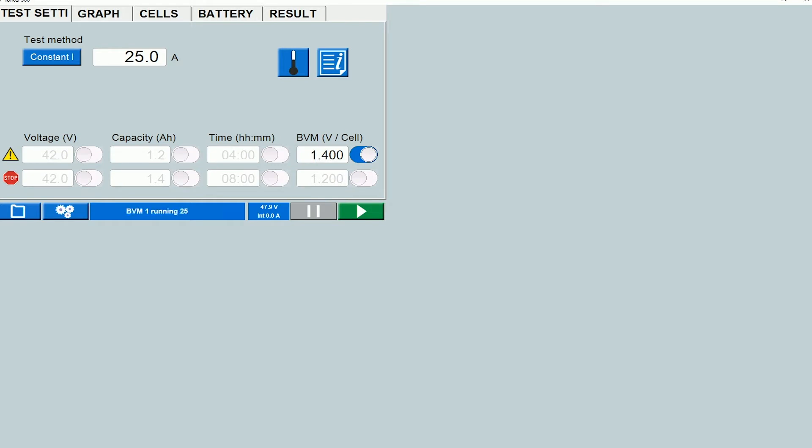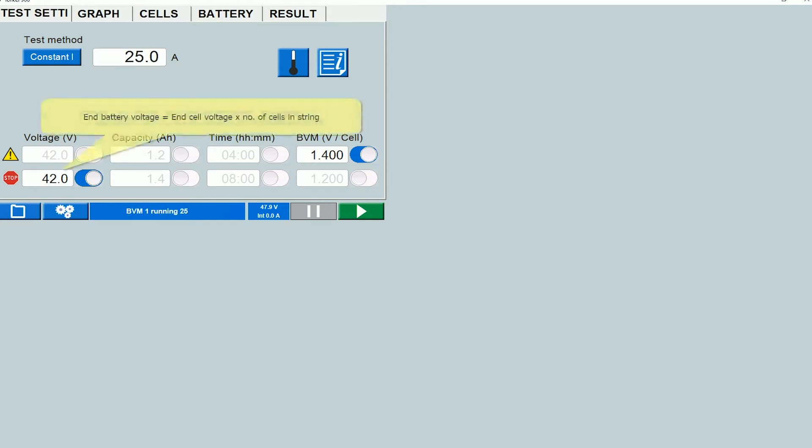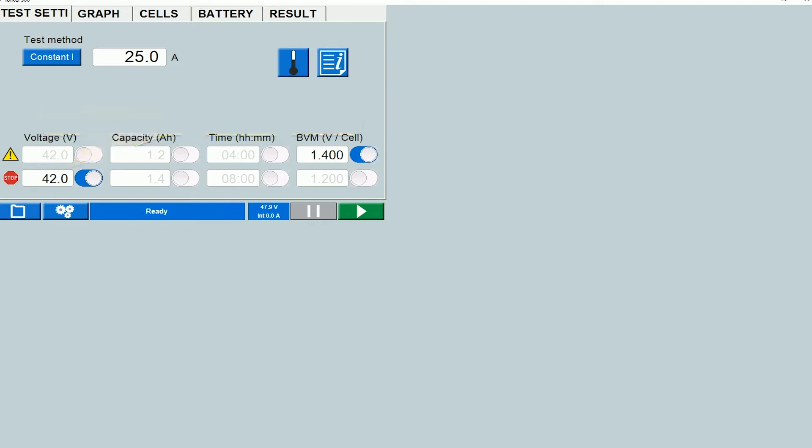I can also set a stop limit on the overall battery voltage. So when I enable this, what this means is that the instrument will stop the test when the battery voltage drops down to 42 volts. Now you would enter whatever the end voltage is for the battery string that you're testing over here.